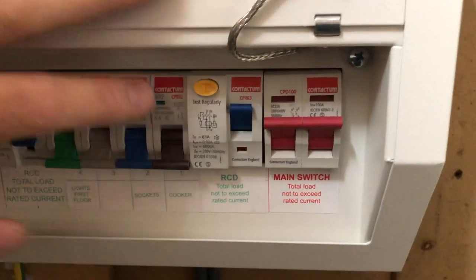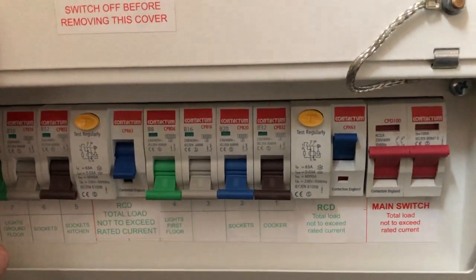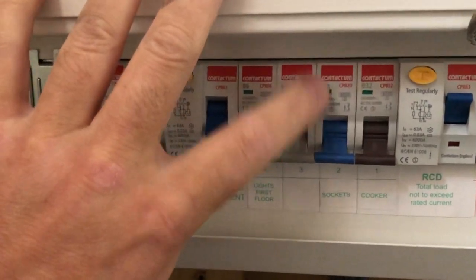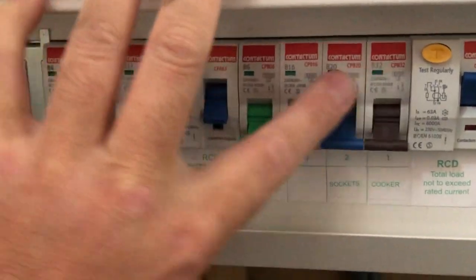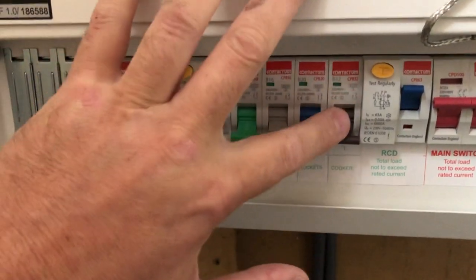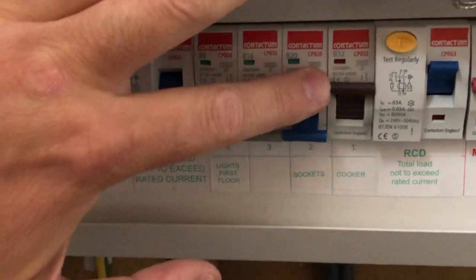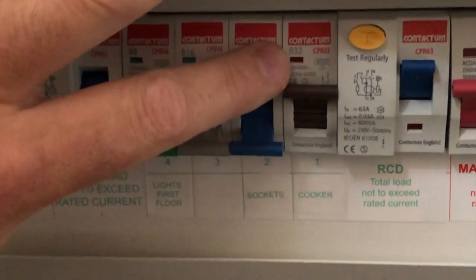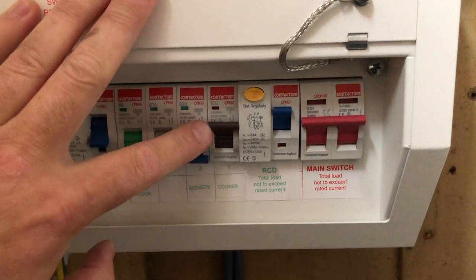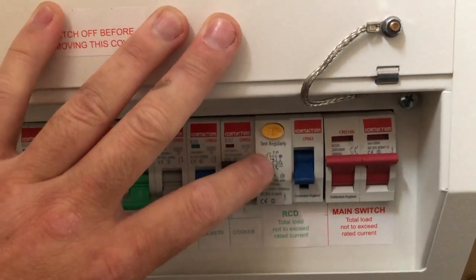One of the biggest problems with these is usually nuisance tripping, and that occurs mainly due to things that are plugged in, or occasionally a bulb that could blow. The procedure to follow is quite simple. These are what they call circuit breakers and each one controls a circuit — this one's cooker, socket, then lights for the first floor. If a breaker trips out, there's been a problem that's occurred somewhere in the circuit.